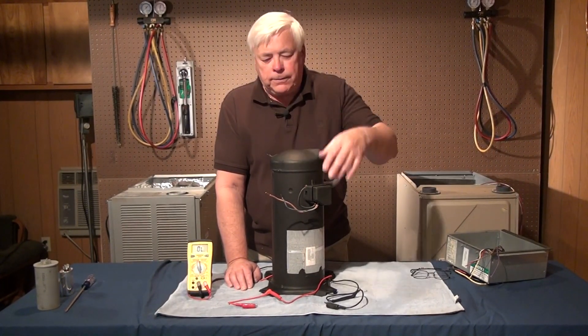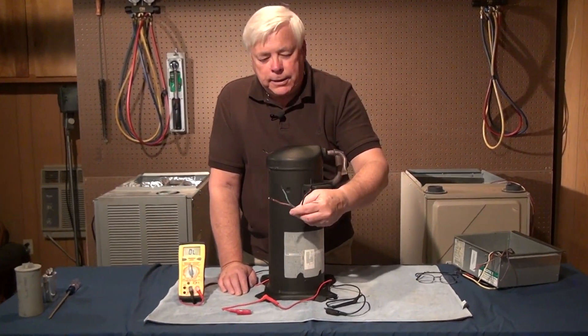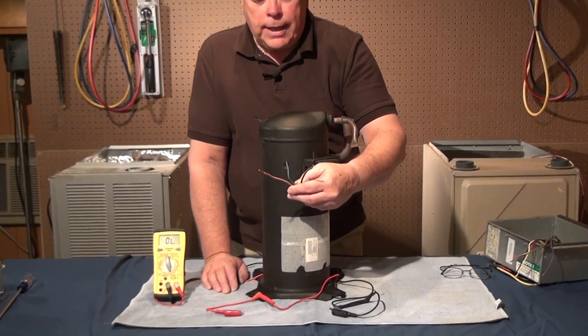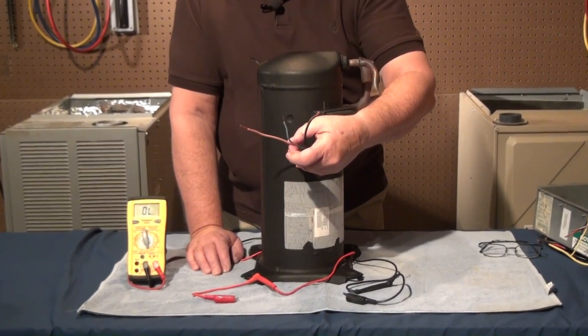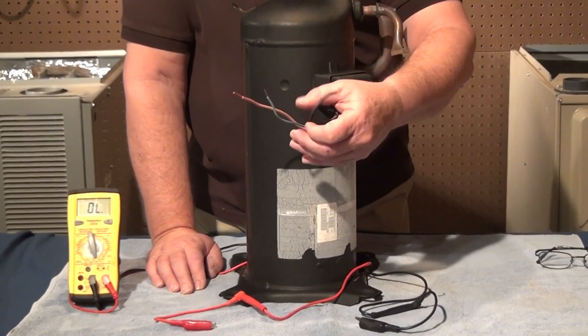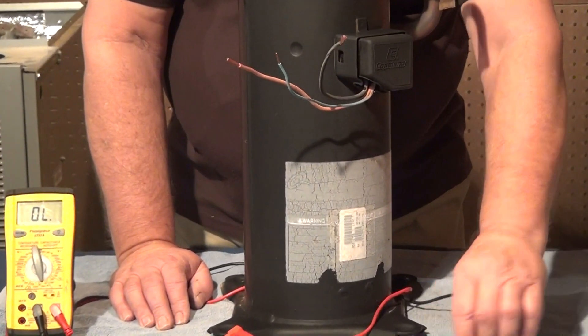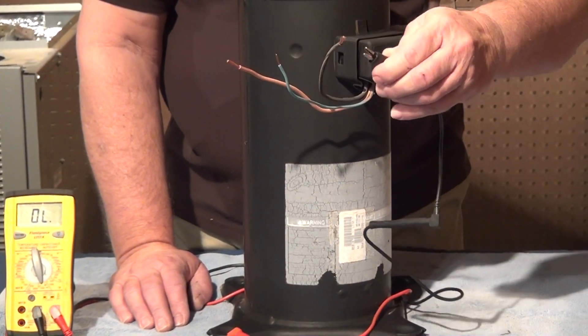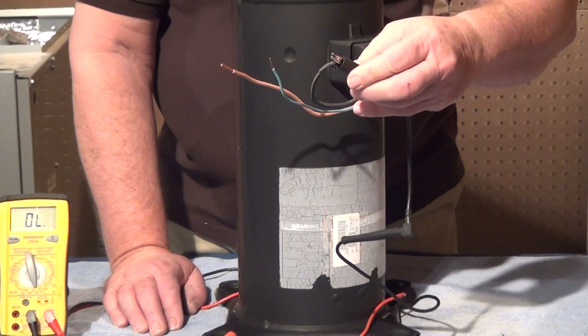So in order to completely troubleshoot this problem situation, we need to make sure that we do a test of this compressor from an electrical perspective, and what we've done is we've isolated the compressor here and we have the three wires that lead to the common, the run, and the start windings of the compressor. What we're going to do is do an electrical check to find out exactly what may be going on with this particular compressor.